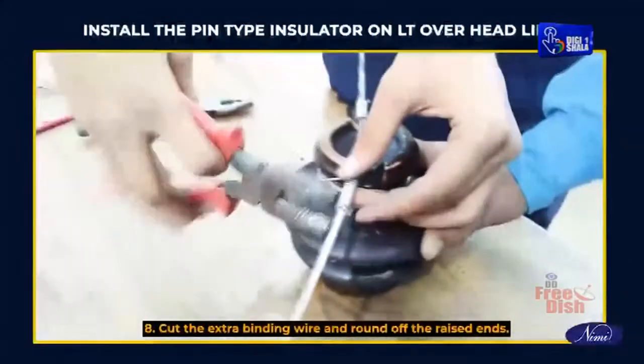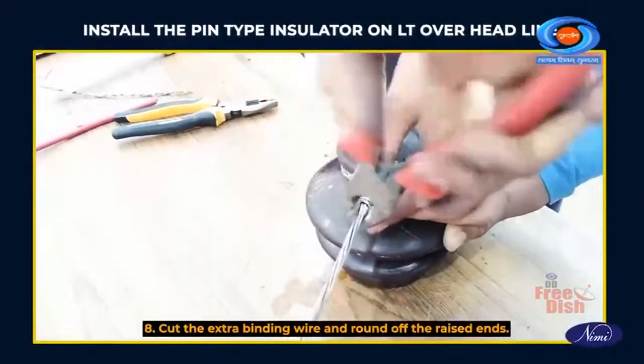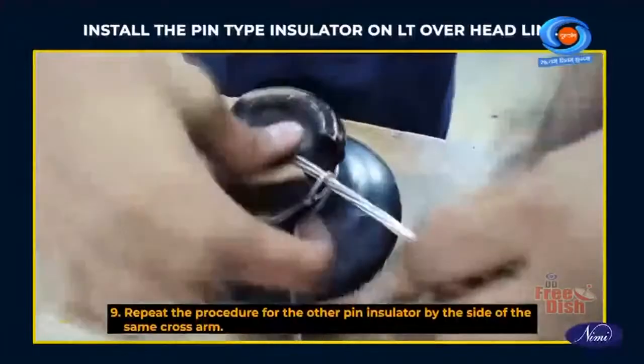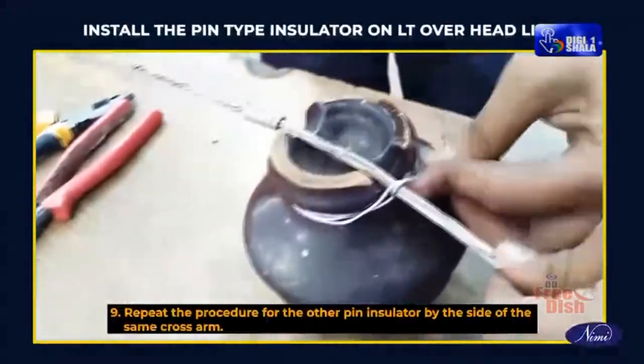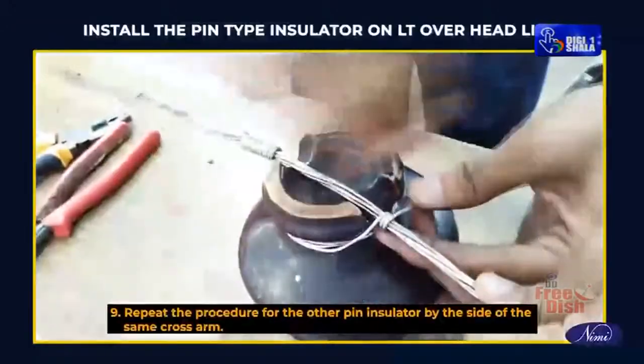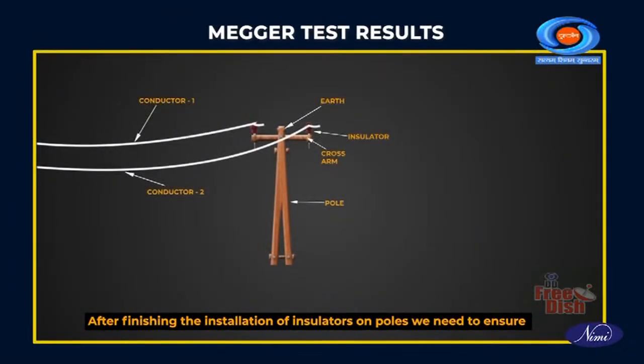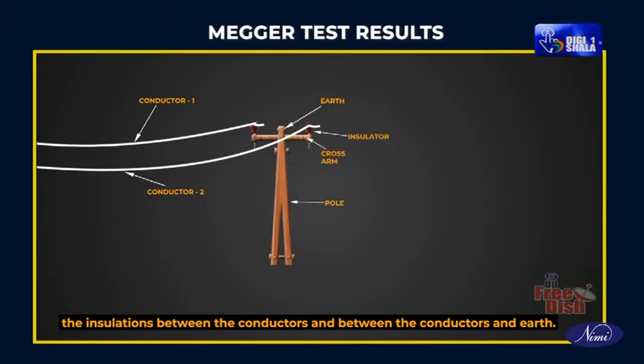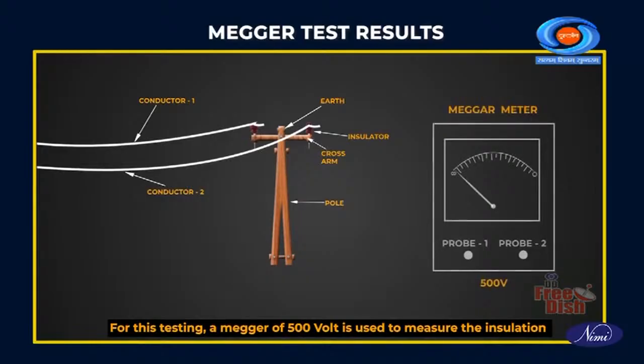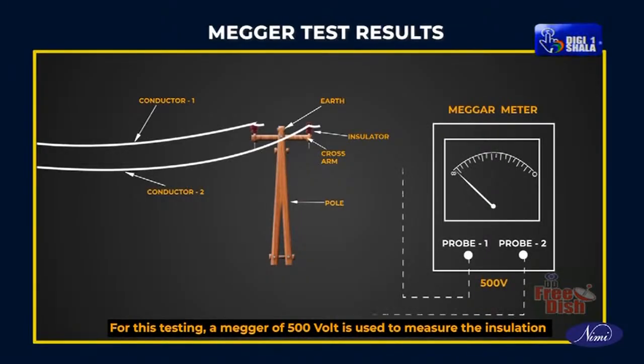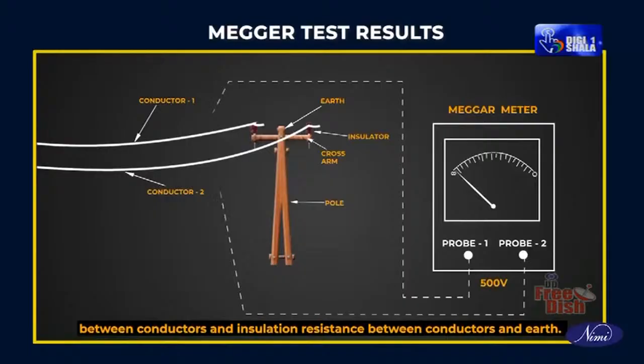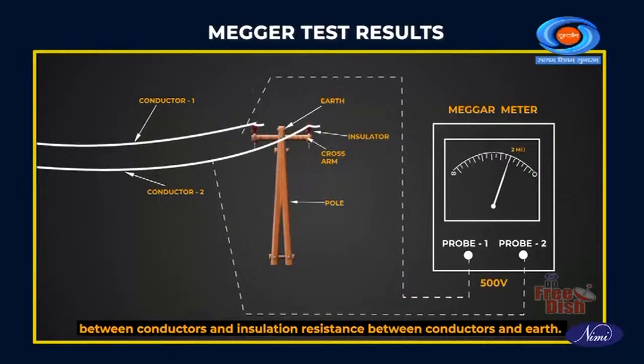Cut the extra binding wire and round off the raised ends. Repeat the procedure for the other pin insulator by the side of the same cross arm. After finishing the installation of insulators on poles, we need to ensure the insulations between the conductors and between the conductors and earth. For this testing, a megger of 500 volt is used to measure the insulation between conductors and insulation resistance between conductors and earth.